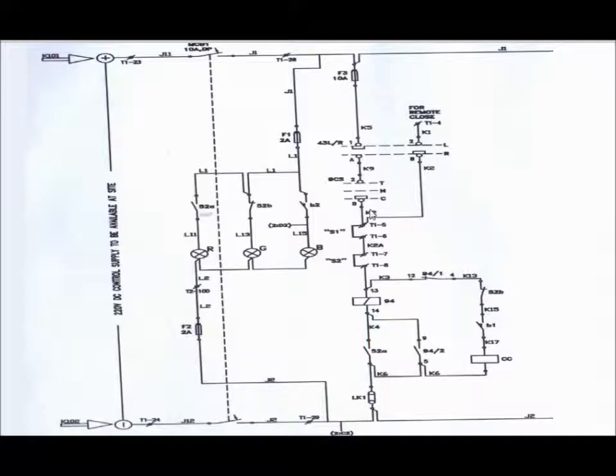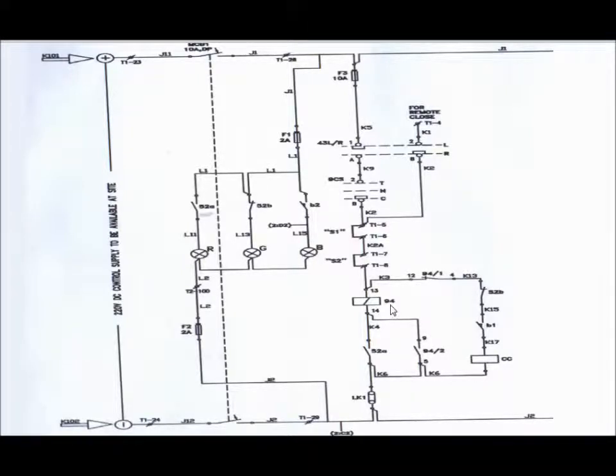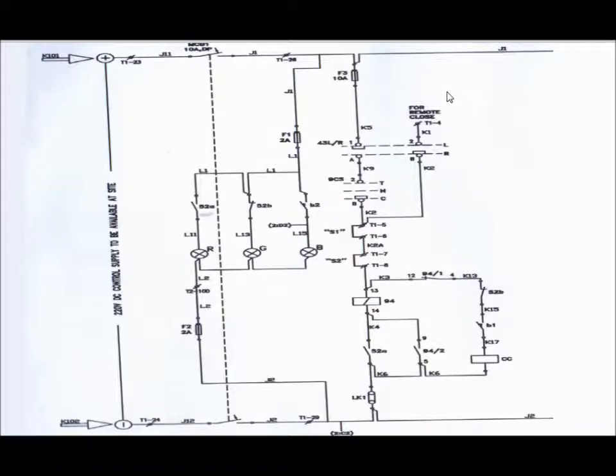Now if we give another pulse from the closing control switch, it will not go to the closing coil further. Instead, it will go to the 94 anti-pumping relay via the auxiliary contact of the circuit breaker. As soon as this coil energizes, its NC contact opens and it remains energized as long as the control switch is in close position. This anti-pumping relay prevents another pulse from reaching the closing coil of the circuit breaker. This is the complete local closing operation of the circuit breaker.